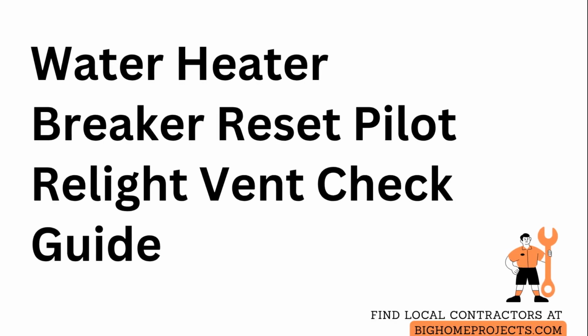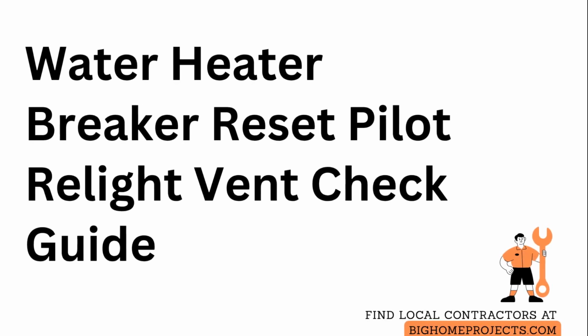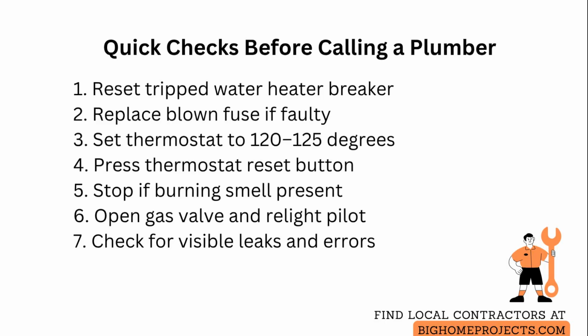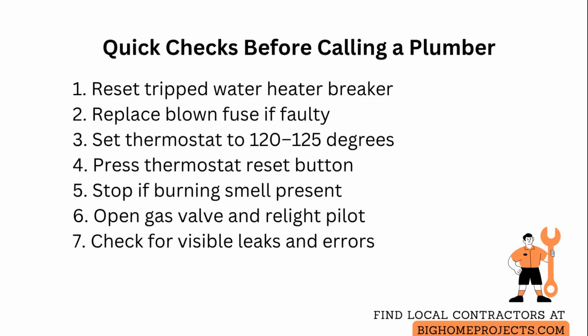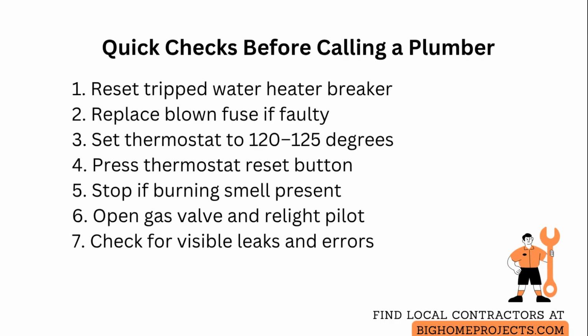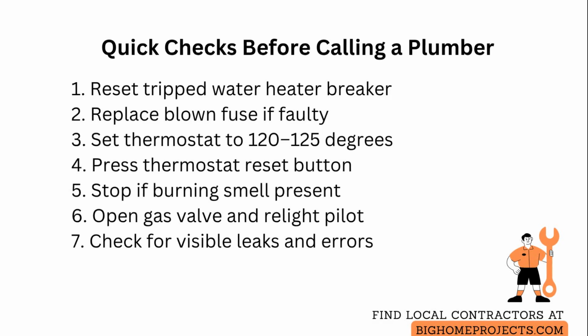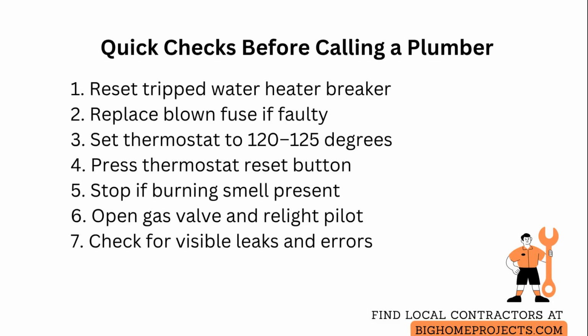Start with the simplest checks you can do yourself to restore hot water fast. If you have an electric water heater, first go to your electrical panel and look for a tripped circuit breaker serving the heater. Firmly switch it all the way off, then back on to reset. If your home uses fuses, inspect the fuse for the water heater and replace it if the filament is broken or the glass looks cloudy.